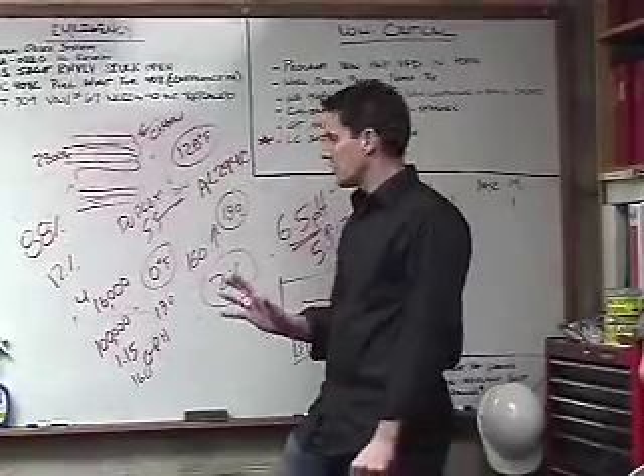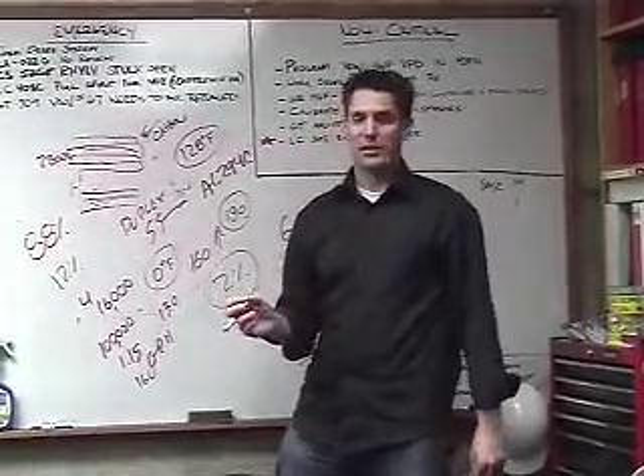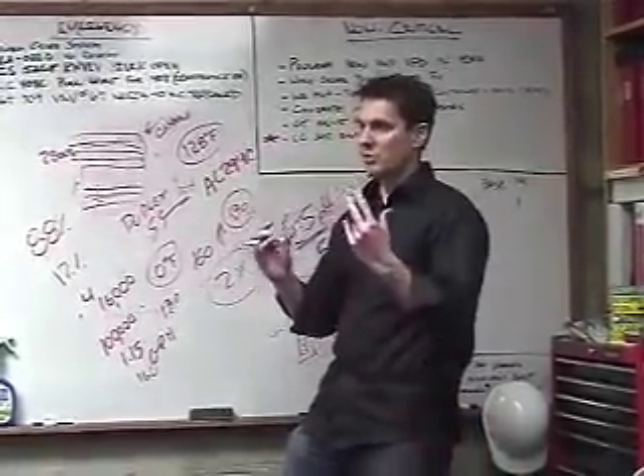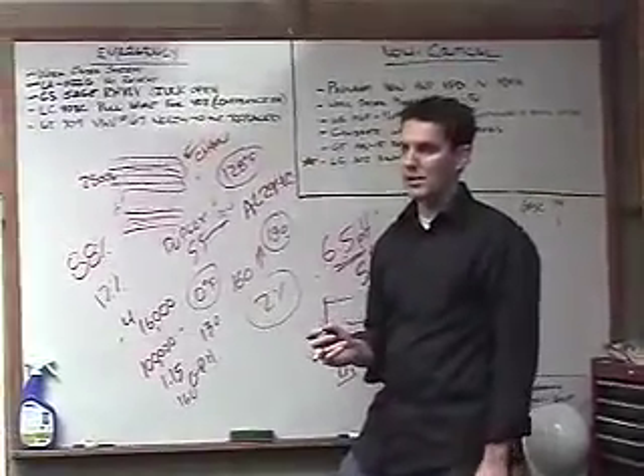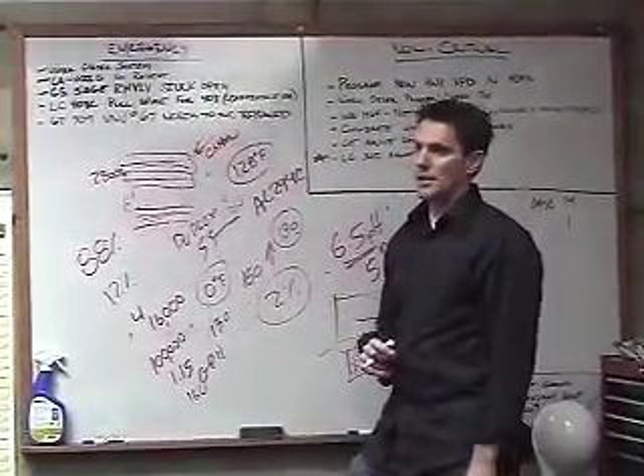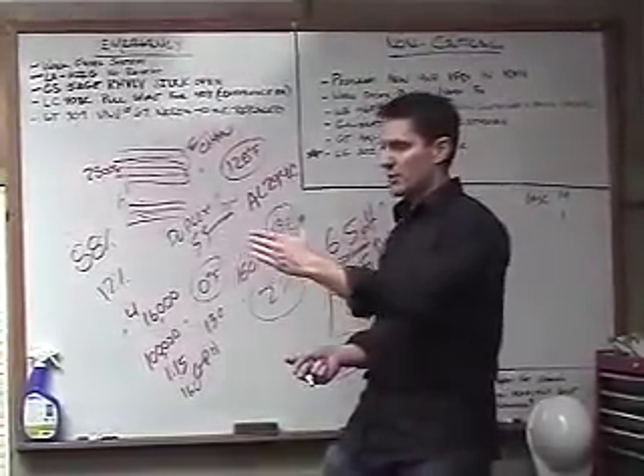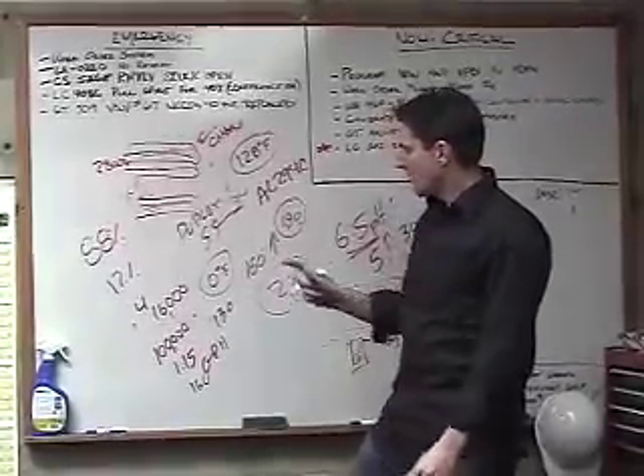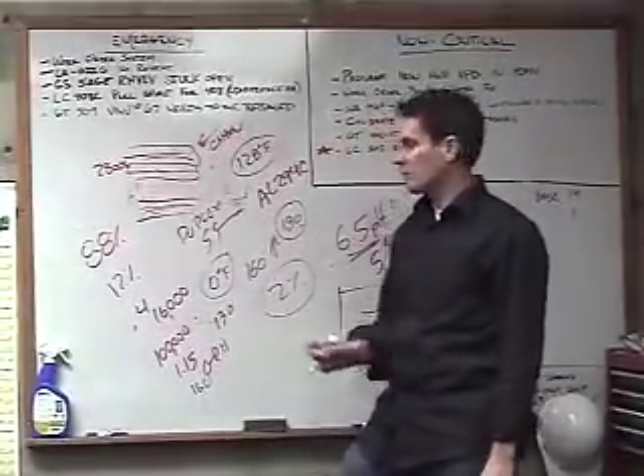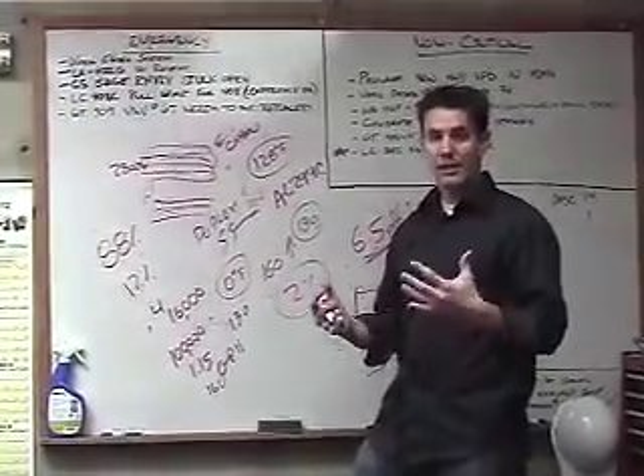Now, to do that, you're going to have to have 60-degree water. Your boilers are going to really be chugging with really, really cold water, so you're not going to get that much. But that's what you're going to want to watch. And again, that's going to be on the coldest day of the year. On the coldest day of the year, your water temperatures might be a little warmer, so you're not condensing as much. So it kind of works in your favor. But that just gives you an idea of how much condensate, or how much water vapor, is forming. And if you condense 100% of that, that's a lot of water. It's a lot of acid.